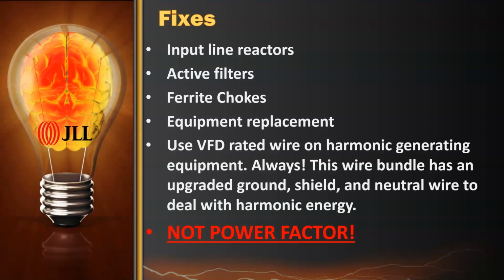Not many. So that's the active filter question I always have. As they wear out, they tend to allow more of that harmonic energy to pass through, and they get hot, and you know, things like that. So I'm not a big fan of active filters. And the chokes don't wear out. They're good forever, correct? Active filters do wear out. No, the chokes. The chokes don't. Yeah, the chokes just sit there. There's an iron core, you know.